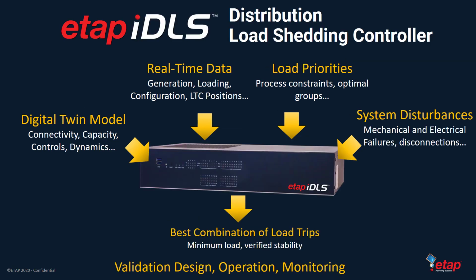Another controller is the Intelligent Distribution Load Shedding controller. The IDLS controller solution uses the digital twin model, real-time data, load priorities, and system disturbance to shed the best combination of loads to meet the required load and optimize quality of service.